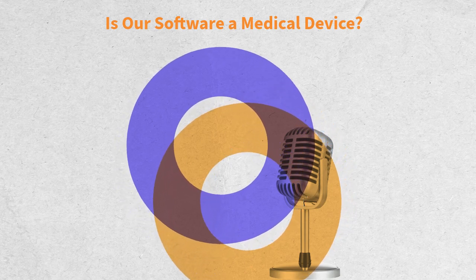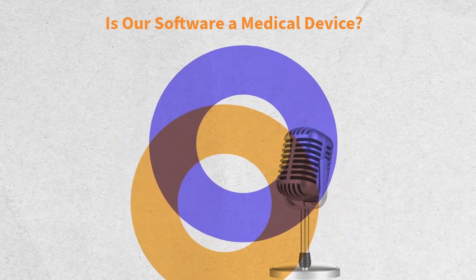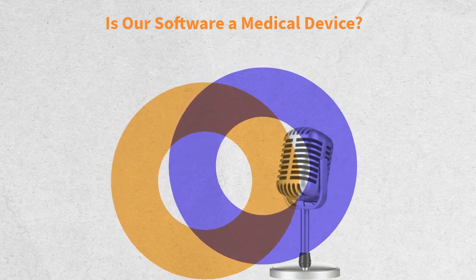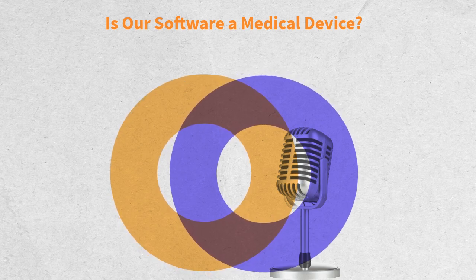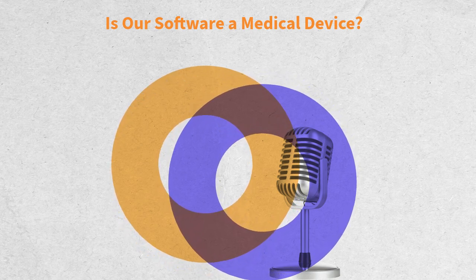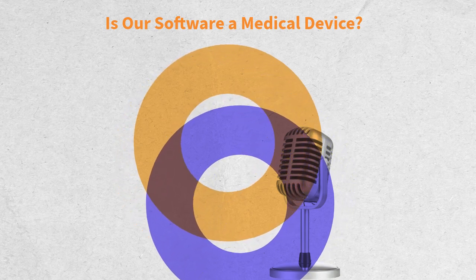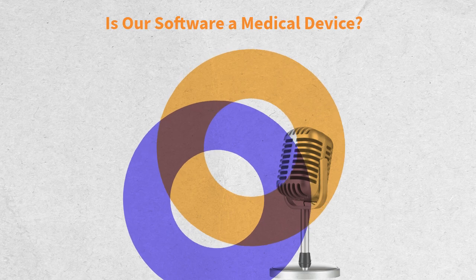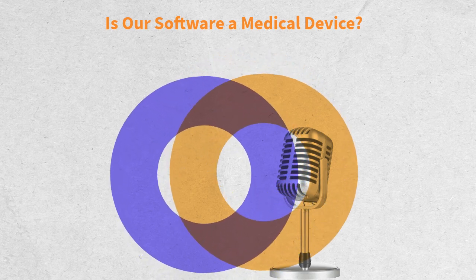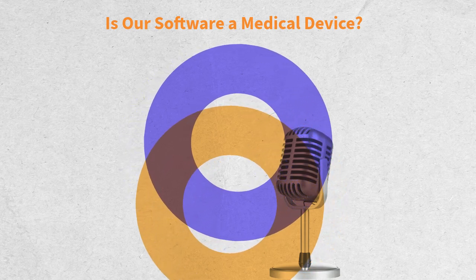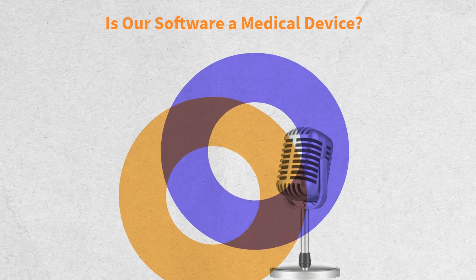Is my software SaMD, software as a medical device? Yes, if your software is autonomous and performs a clinical function with no need of a dedicated medical hardware. If a computer or smartphone are sufficient to make it run and has a clinical impact, for instance supporting decisions, it falls into the definition of an SaMD.